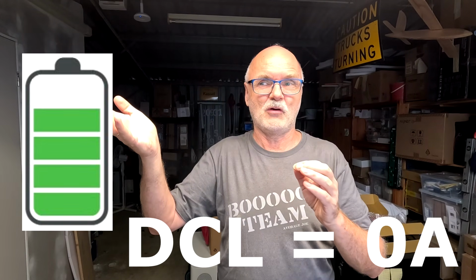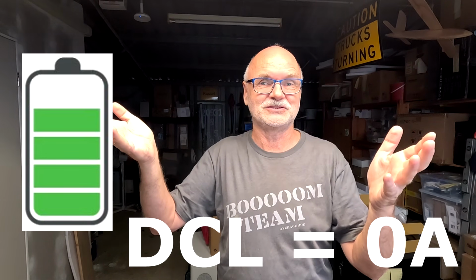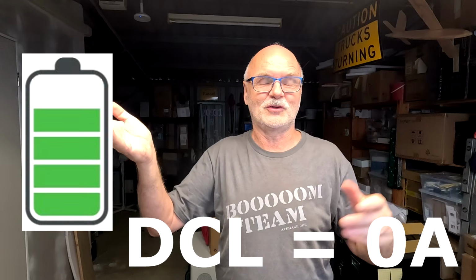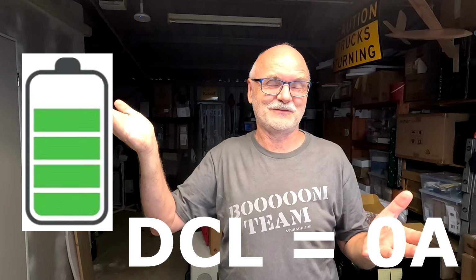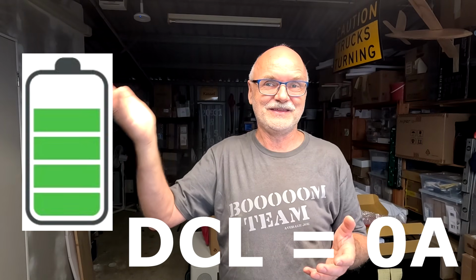So even if it sits on 1 amp, I can take whatever I need, it doesn't matter. But if it sits on 0, it signals to the inverter that something is wrong with the battery, it is totally depleted, DCL is on 0, turn off. Not good. Exactly the same happens for everyone with hybrid inverters that have grid connection and battery. If your DCL is on 0, the inverter would not take any juice from the battery, it would take everything from the grid. But what if your grid is failing? Your battery has recovered through this dynamic state of charge protection to like 60-70%, and your grid fails. Your inverter will get a signal from the BMS, DCL 0, and you'll be in the same off-grid situation.